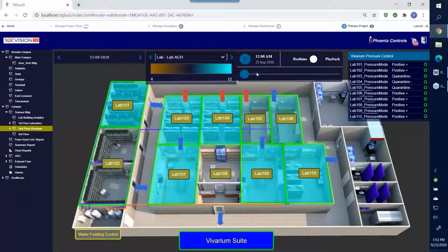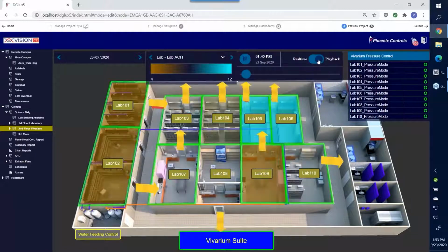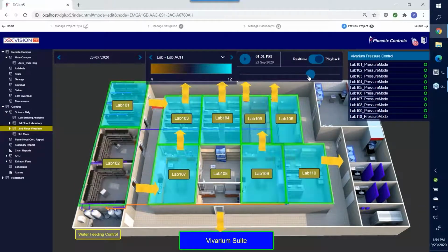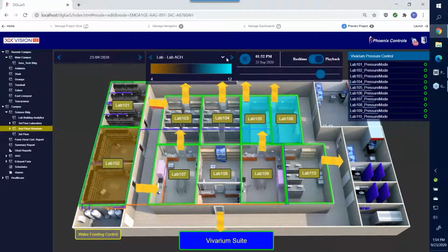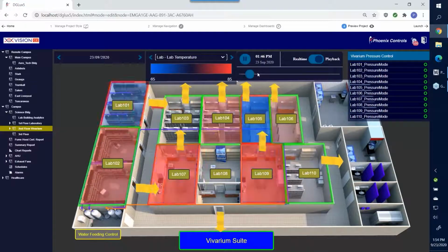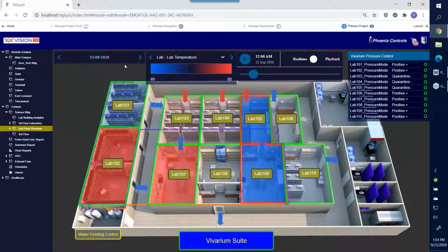Another unique aspect is that in addition to running in real time, we have the ability to switch to a kind of DVR control. Right now it's just running, but we can grab this and look at specific times or time intervals, looking for hot spots to assess what's happening if we expect a certain air change rate or temperature. It allows us to find hot and cold spots and see cycling you probably wouldn't find otherwise. This DVR control is available for any variable within the system.